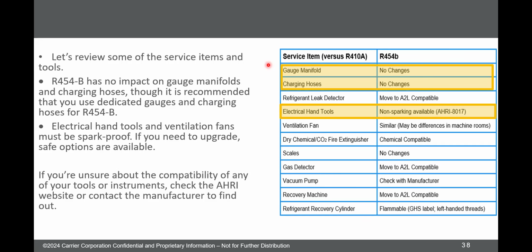Analog gauges, that's different, obviously. There's no updating on those. So it is what it is. You can use your R410A analog gauges on R454B if you wish. You just have to not look at the pink band of temperature in there, completely ignore the existence of that, and just read the pressure only, because the gauges measure pressure, and that just correlates to a temperature. Read the pressure, and then take that pressure and go to the chart I showed you a few minutes ago and see what temperature that correlates to. Obviously, after 2 or 3 jobs, that's going to get annoying, and people are going to want to just go ahead and buy 454B gauges that already have the sticker with the right temperature in the back of the gauge, so they don't have to go back and forth with a chart. So I'm assuming you guys have analog gauges at the counter for sale at this point. I know last year when I looked, we didn't have anything, but I'm assuming you got it by now.